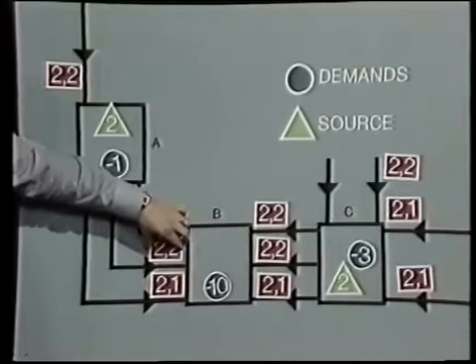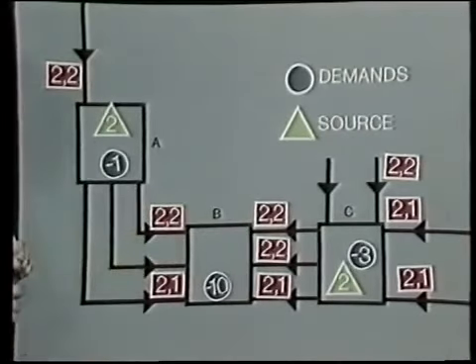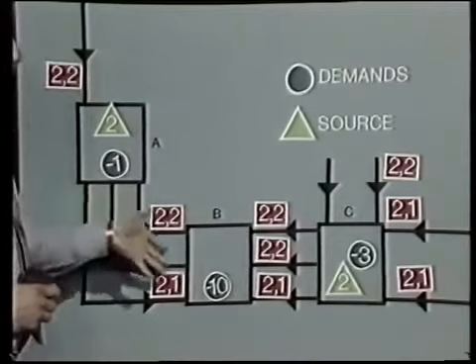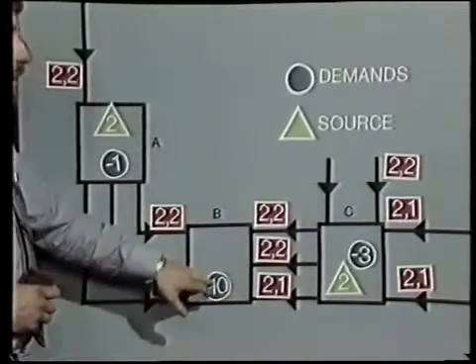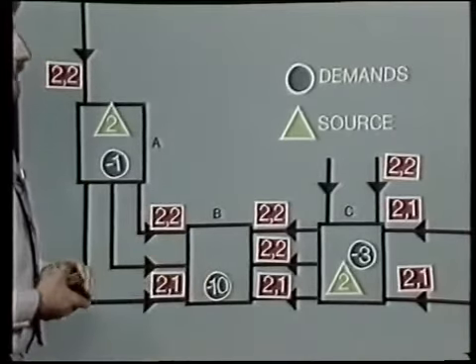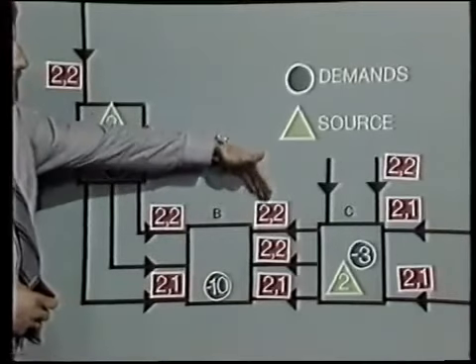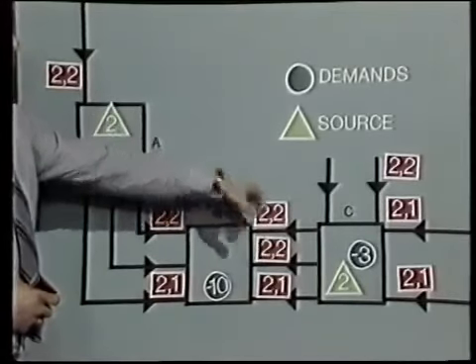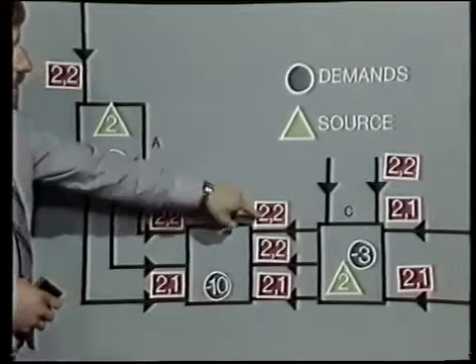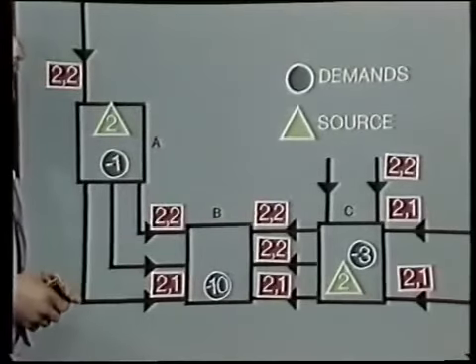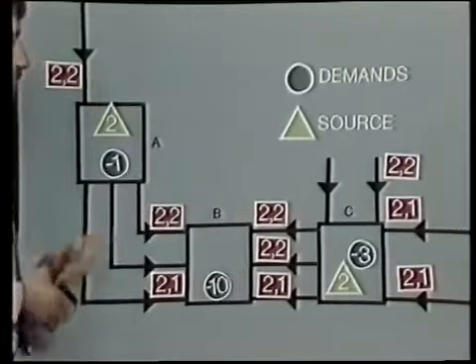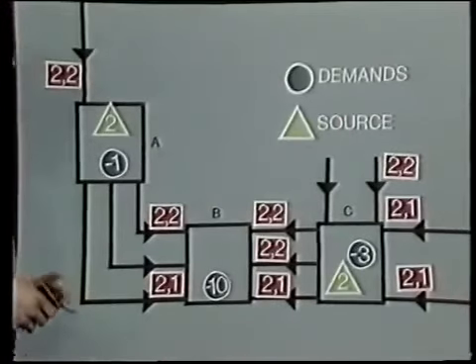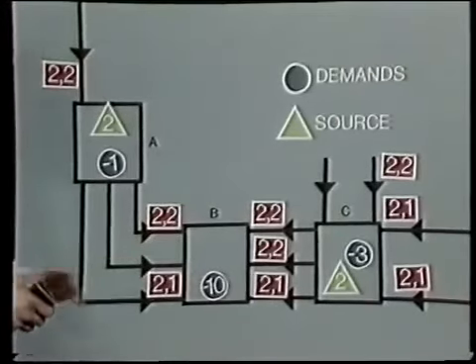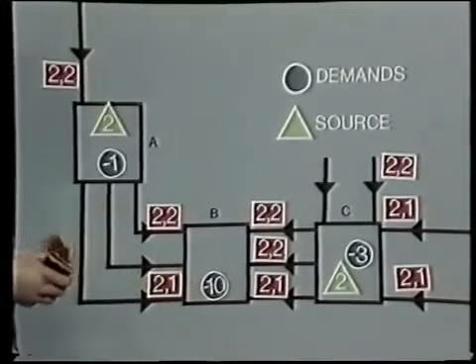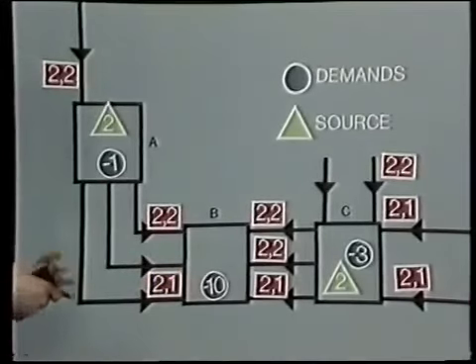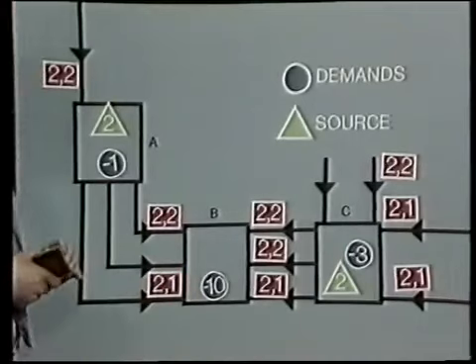We can do that by having 2 on one line and 1 on the other, so we're now supplying 3 into B. We require 10 — where do we get the other 7? There's actually no way we can get 7 gigawatts along these 3 lines because they have a maximum capacity of 2 each; we can only get 6 in. The system would not cope with that unless we brought on another power station in the area of B, which again would take lots of time to run up all the various equipment.